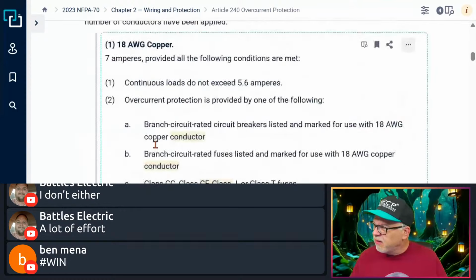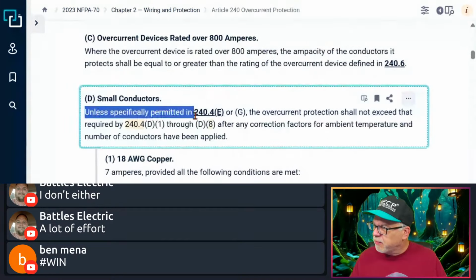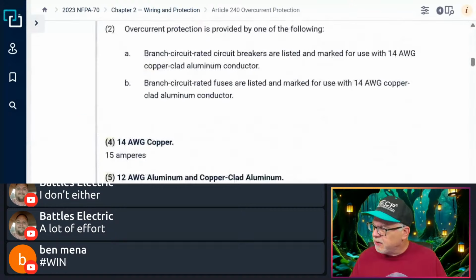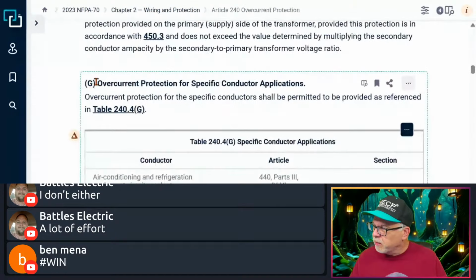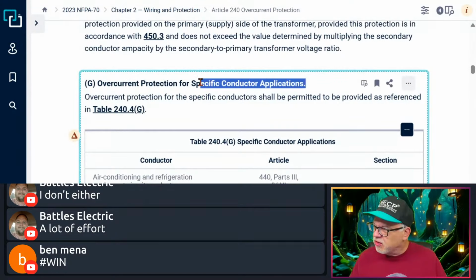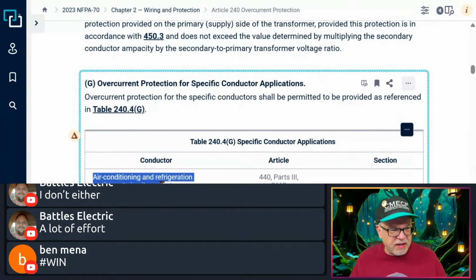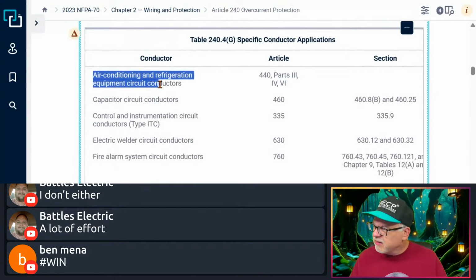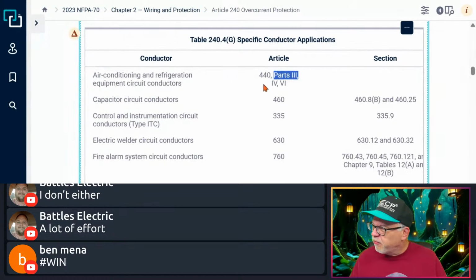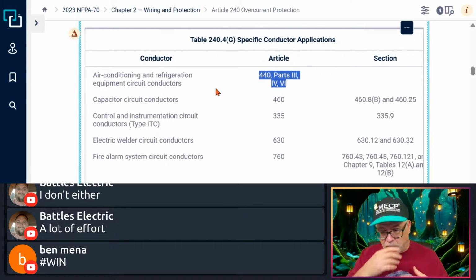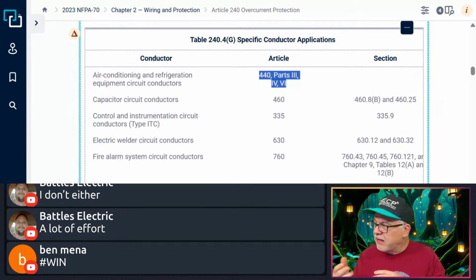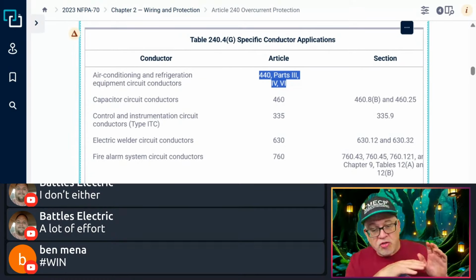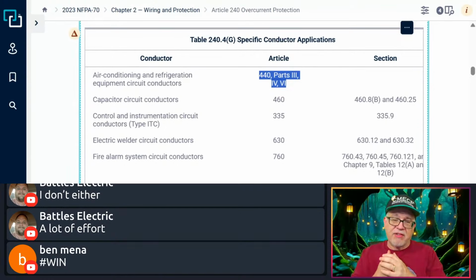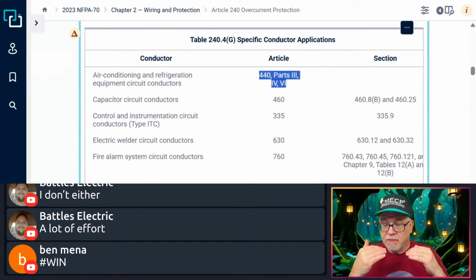But because of this statement right here, unless specifically permitted, we're going to go down and look at (G), okay? (G) is overcurrent protection for specific conductor applications. Now you notice right here, air conditioning. That's what we've been talking about. In Article 440, Part 3, Part 4, and Part 6, it gives us the instructions for doing all this sizing. And basically, it says, you know what? Ignore those small conductor rules, because as long as I have a conductor that can handle the minimum ampacity, and that's on the nameplate, which is 23 amps, follow the nameplate.